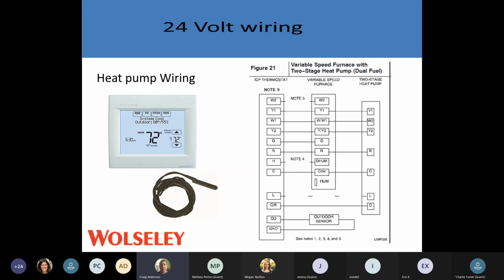Heat pumps are designed on a split system so that if the reversing valve failed or something failed, they will still have heat. So when we go into air conditioning, we're always going to be energizing our O for our reversing valve. And then we're going to be energizing our Ys, depending on what stage of cooling you're going to be asking for. So 24 volts to your outdoor unit on those connections in cooling mode.